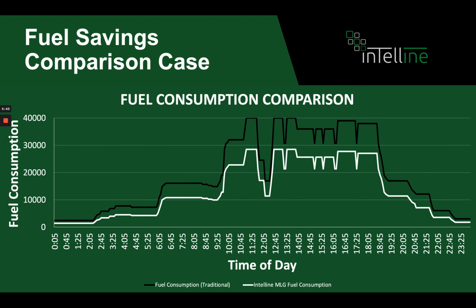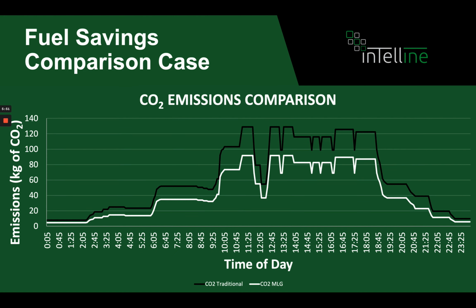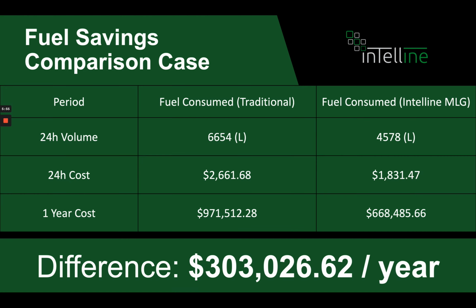Now this graph shows the obvious reduction in fuel consumption as a result of higher thermal efficiency and more effective load matching. And similarly, this plot shows the consequent reduction in CO2 emissions. Now I move through these plots quickly as the final figures are much more meaningful. In 24 hours, the traditional generator uses just over 6,600 liters of diesel fuel. And for the same demand, the MLG uses just under 4,600.